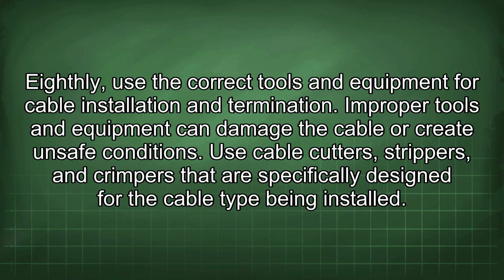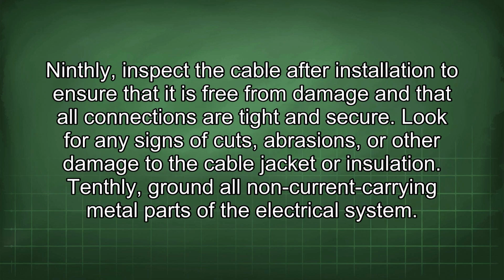Eighthly, use the correct tools and equipment for cable installation and termination. Improper tools and equipment can damage the cable or create unsafe conditions. Use cable cutters, strippers, and crimpers that are specifically designed for the cable type being installed. Ninthly, inspect the cable after installation to ensure that it is free from damage and that all connections are tight and secure. Look for any signs of cuts, abrasions, or other damage to the cable jacket or insulation.